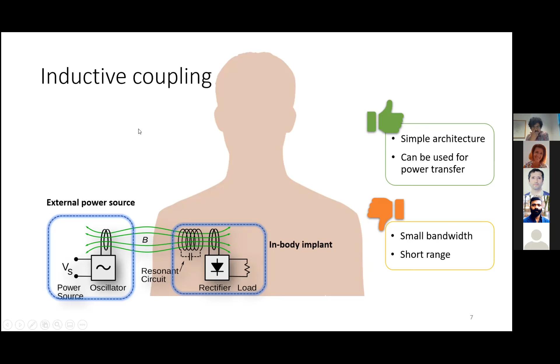One thing I actually forgot to mention about inductive coupling: one of its main problems is the alignment of the coils. For good communication, the coils inside the human body need to be aligned, because if there is a small misalignment of the coils, then the communication is not good. So this is another major problem of inductive coupling.